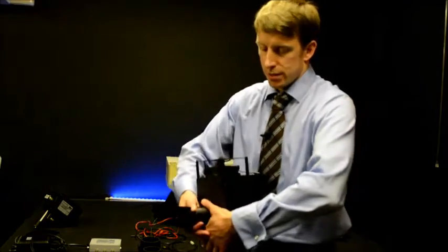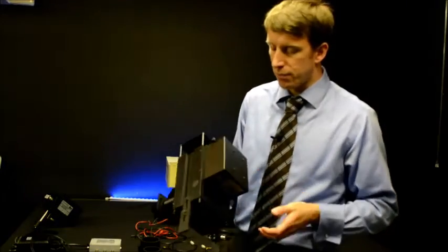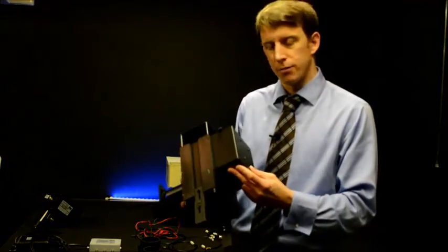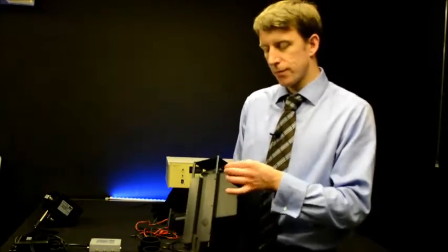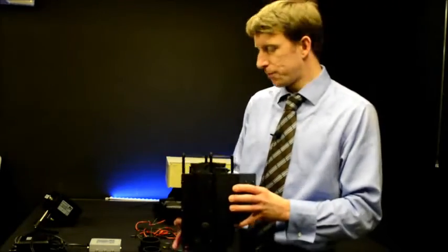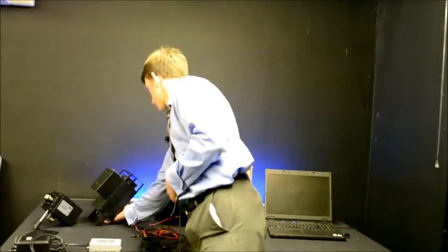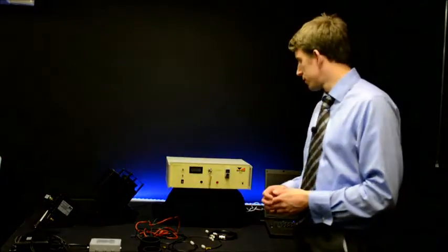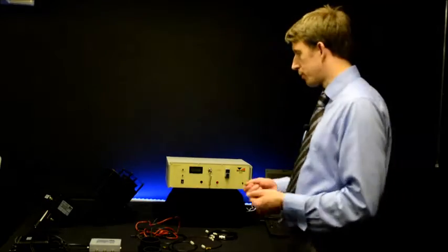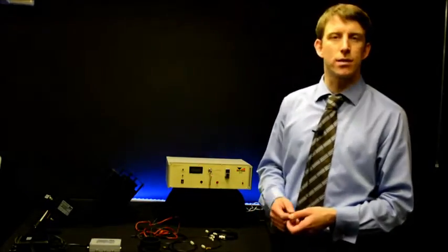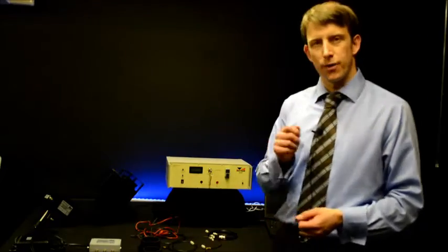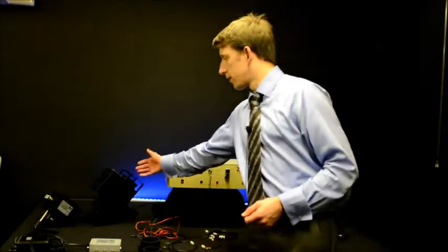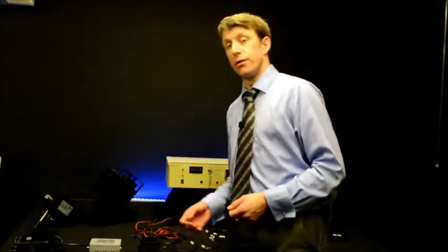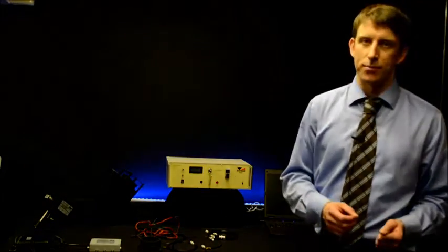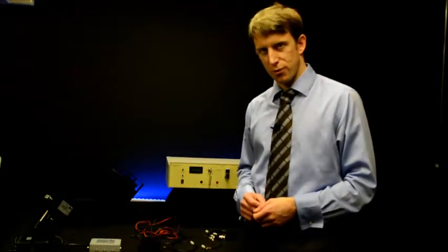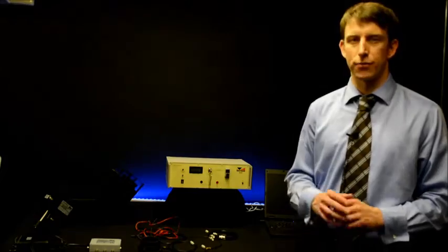This source is operated from a 605 constant current power supply with red and black current inputs underneath the starter unit and a fan input equally. The 605 constant current power supply is used to operate both the IL7 xenon lamp and the CL6 calibration standard. One should be very careful about the current setting. The xenon lamp operates at 8.5 amps. The irradiance standard operates at 6.3 amps. 6.3 amps here is no problem. 8.5 amps on the CL6 will result in lamp failure.